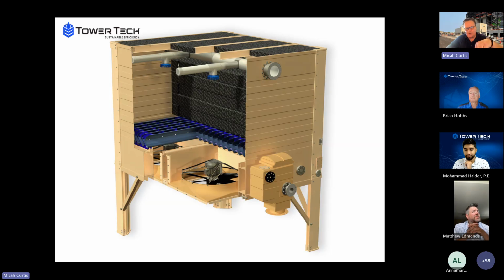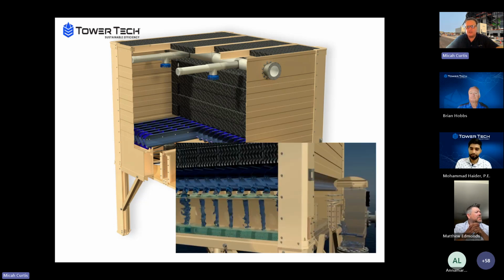You don't have to put in a special drift eliminator consideration. You don't have to put a sweeper into the tower. You don't have to worry about it growing algae. It comes minimizing Legionella risk. Here is a picture of the flow-through basin Muhammad referenced, where the water moves. This is a cutaway through the basin, much like piping inside of a wall. You can't see it or touch it.